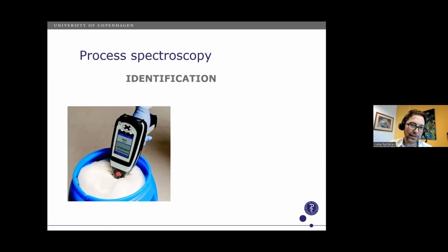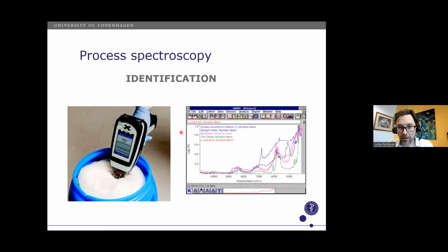The light is coming out from the top of the instrument, and you control the measurement by using almost a pistol type of solution. You measure the sample here, and then you have the data in your spectrometer. This gives you quite a lot of freedom to move around with this handheld instrument and collect properties of material. This is commonly used for ID purposes.